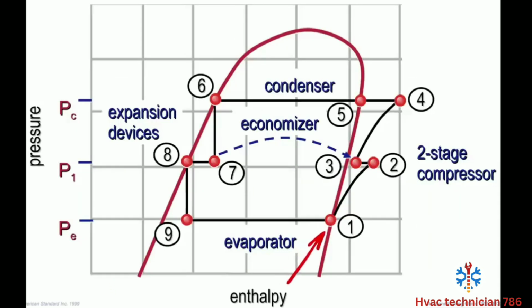I need to quickly show you this PE chart, pressure enthalpy, specifically here at the economizer section, what the economizer is doing, and this is for a CVHF specifically. We leave the condenser at point 6 here. This is our liquid line where we're a high pressure liquid refrigerant. When we go through the first flash plate into the chamber, we are then in the economizer at point 7 where we're a saturated refrigerant. And anywhere in the middle here we're at saturation. Over here we're at subcooling, over here we're at superheat. This is our discharge superheated gas flowing from the outlet of the compressor into the condenser over here.